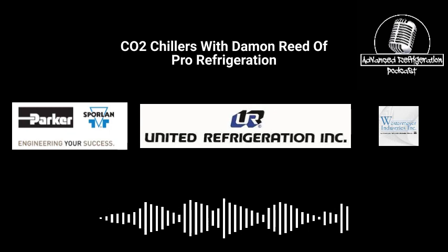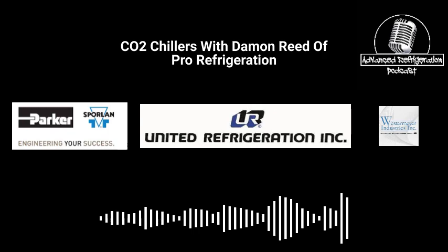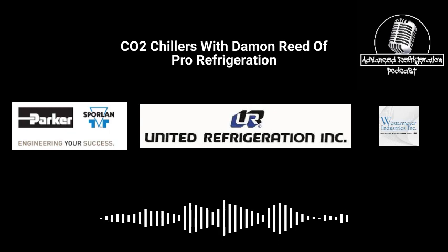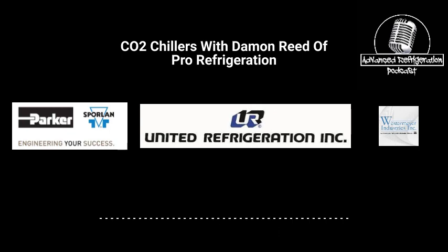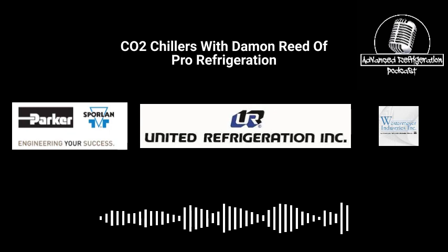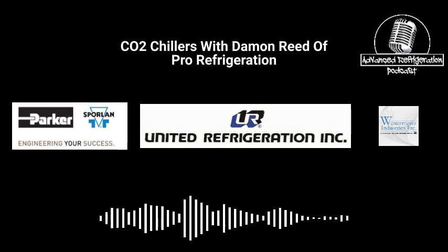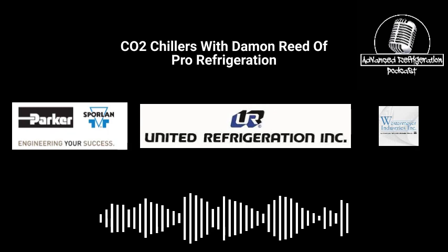In a place like Alaska, at what point do you just bypass the rack, hook up a dry cooler to whatever process you're trying to cool, and just run a basic dry cooler for refrigeration? Absolutely. Some of the systems we built for them, on the synthetic side, we did that. You just run a dry cooler on your return line, but then you've got to watch that fluid coming back: if the flow shuts off, how does it drain back into the reservoir? So nothing's ever as easy as it sounds. It's kind of what you learn. Well, yeah, because you're obviously not running glycol down to a -40 freeze point.